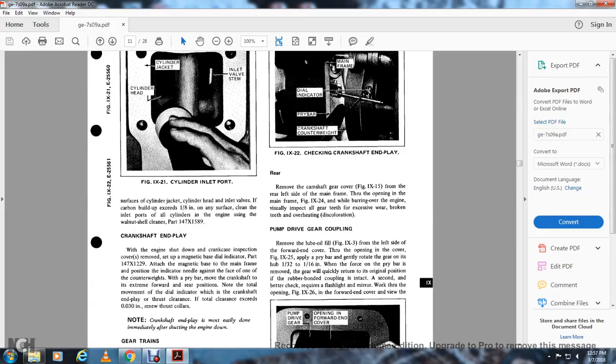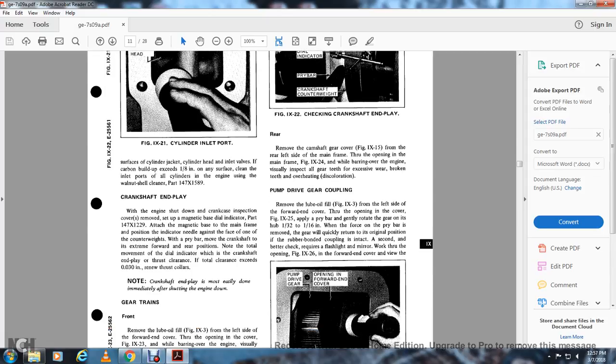Crankshaft end play: With the engine shut down and the crankshaft inspection cover removed, attach the magnetic base indicator (part 147X1229) to the mainframe and position the indicator needle against the face of one of the counterweights. With a pry bar, move the crankshaft to its extreme forward and rear positions. Note the total movement of the dial indicator — this is the crankshaft end play (thrust clearance). If the total clearance exceeds 30 thousandths of an inch, renew the thrust collars. Note: crankshaft end play must be measured immediately after shutting down the engine.